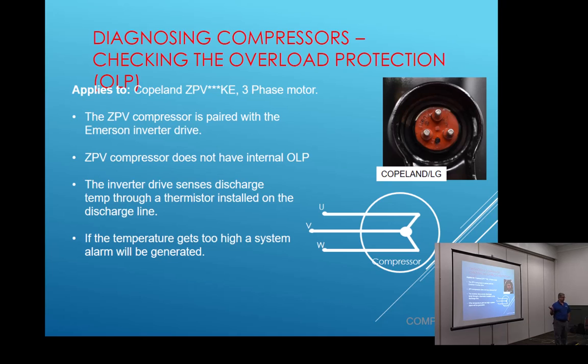Okay, so if you go out there looking for one and you've got inverter faults, not only checking the inverter, and we're going to teach you how to do that today, but we want to check that compressor also. Pull the plug off, turn the power off. Yep, peg to ground, and then across each leg.